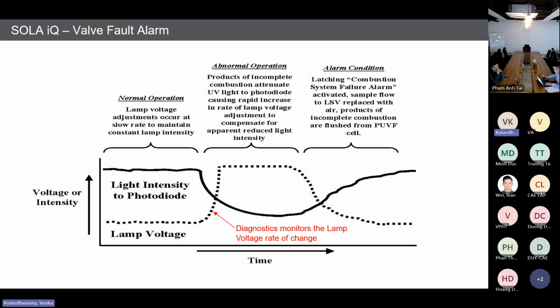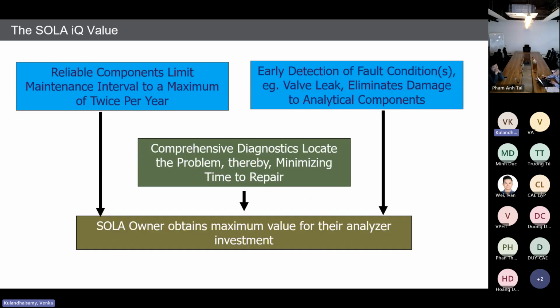This functionality is not in a GC or in other analyzers. If in a GC any excess sample or high range process goes in, the whole column will be contaminated, and you cannot avoid that situation. But with our SOLA IQ, thanks to the valve fault, we can avoid that kind of situation. So we can safeguard the pyrolyzer and the PUVF bench. That's why we can say the downtime and repair cost is very low compared to a GC or other sulfur measurement solutions. Understand? Is it clear now?